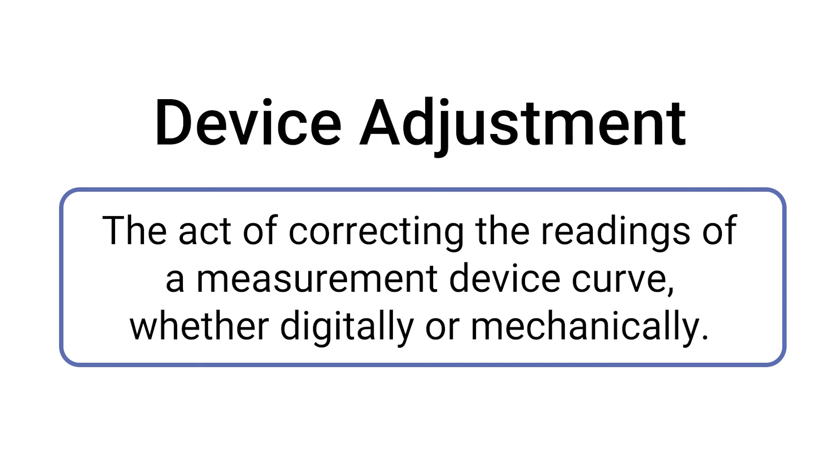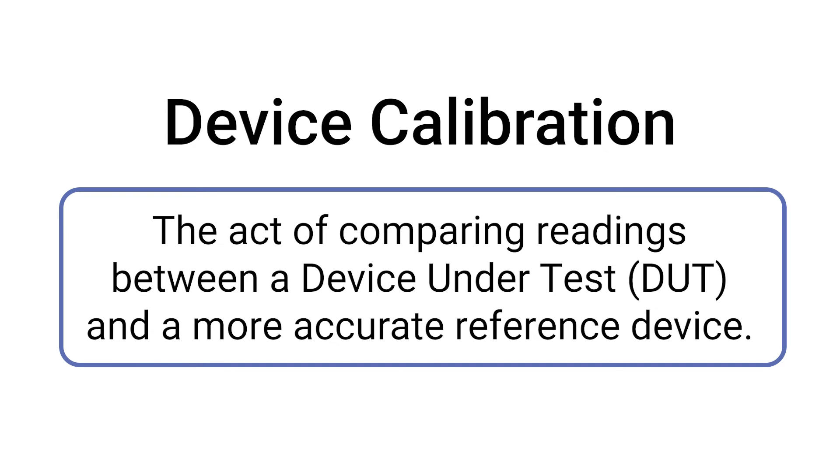This act of correcting the linearity of these measured values is what it means to adjust a measurement device. This is different from a calibration, where the device may already be within specification and not need to be adjusted.